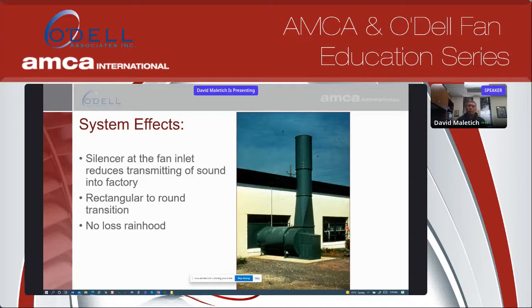This is actually a good system. In this case, we have a fan exhausting from a factory. We have a silencer at the inlet of the fan. Silencer does two things. One, it acts as a straight piece of duct, so we don't have any turbulence going into the fan. Secondly, it minimizes the transmission of noise from the fan back into the building.